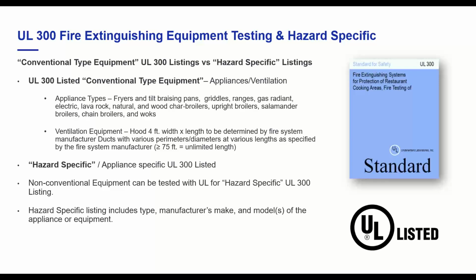UL 300 specifically, a lot of us in the restaurant industry and restaurant fire suppression industry have heard of and might be familiar with. UL 300 is the standard that identifies how to test specific appliances and relates more specifically to the fire testing of those appliances. So it's going to identify the appliance types: fryers, tilt braising pans, griddles, ranges, broilers of many different types and fuels, and then woks. So it lays out a generic type of appliance coverage for each of them.